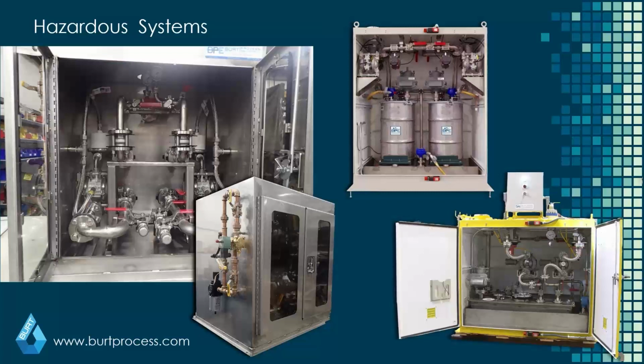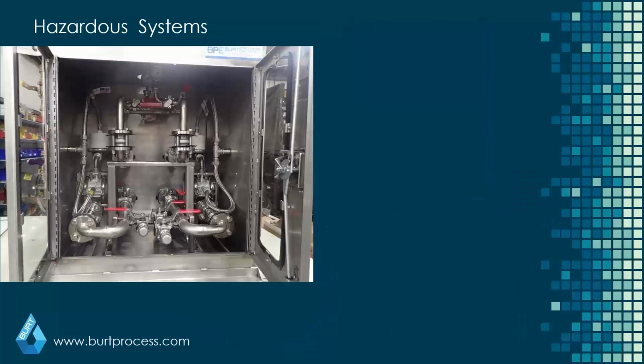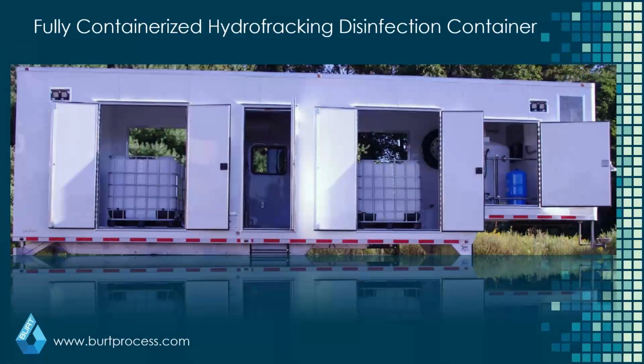Of course, and there are different ways to look at this. When you're talking about a mobile container, these have a slightly different power connection. These would typically have a plug-in based power connection, like a single 460 volt connection, and then within the container itself, you would have all the necessary transformers and everything else that would power any lighting, utility outlets, things like that.